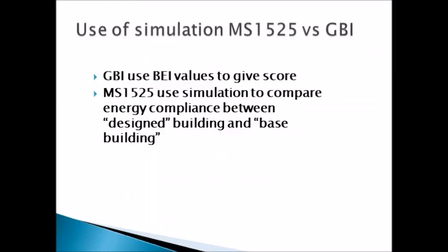Now, to give a clearer understanding of what has been discussed, I would like to conclude with a comparison of the use of simulation between what is required in MS1525 against how it is being used in GBI. So in GBI, you use simulation to provide BEI values to give a score. In MS1525, the use of simulation is to compare the energy compliance, that is the energy used by your design building, and compare it with the base building.